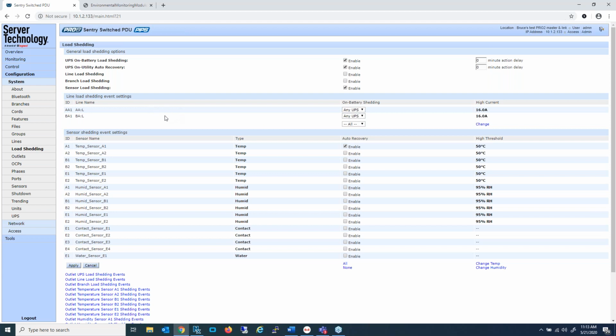We have vastly expanded the feature set and the additional things that you can do with load shedding. I'm going to start with describing line load shedding. Line load shedding is line current, that is current as measured at the input to the PDU. You can set thresholds, and if a threshold is exceeded, we can switch pre-selected outlets off.